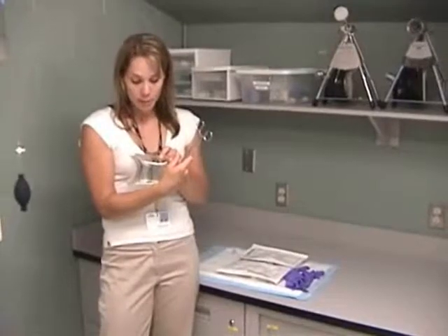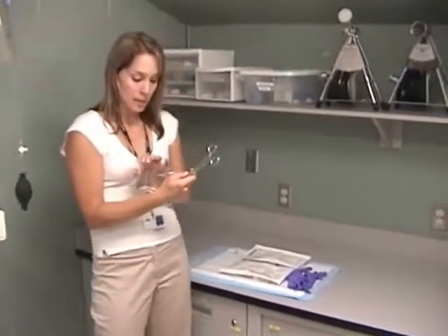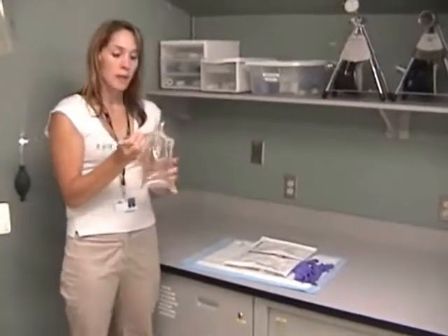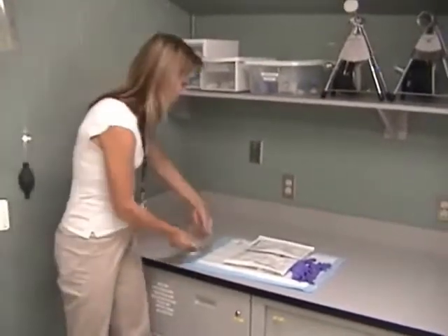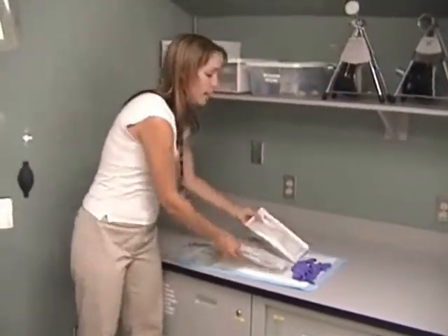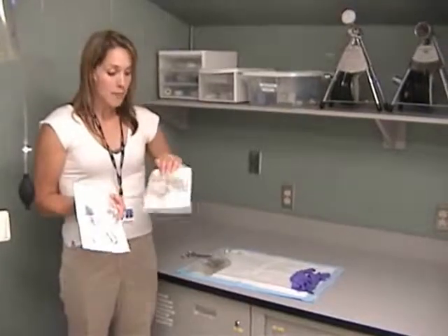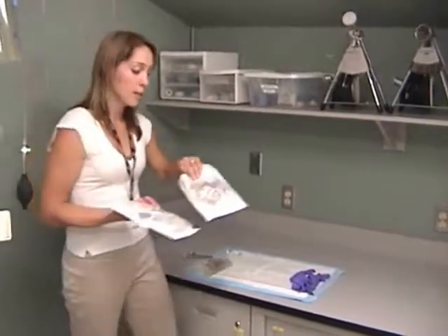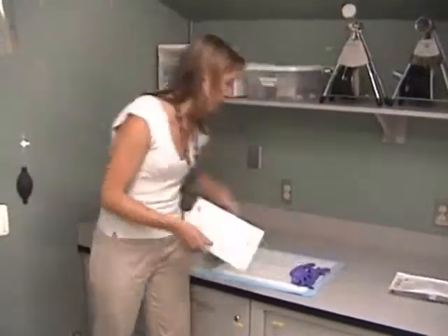These usually come pre-mixed in the hospitals, but if for some reason your hospital is out of these, you can simply use a normal saline bag and mix in the appropriate amount of heparin. Of course, it would be a brand new sterile bag in the hospital. Next, you need a disposable pressure transducer. There's two types out there typically, the three-way stopcock type and the Vamp method type. So for this setup, we're going to use the three-way stopcock.